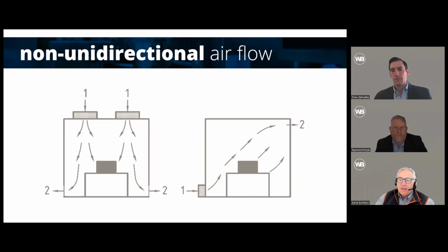Right. And along those lines, another question: do clean rooms recirculate air for energy efficiency reasons, or is it always supplied by fresh air intake? I think you answered that before. In most spaces, yeah, it's really a toxicology issue. In most clean room spaces, it's large recirculation. It's really in pharma or chemistry use or toxic use where you'd want to exhaust that out. And usually when you exhaust that out, you're going to exhaust it out to the atmosphere, out of the building, through another containment filter system to protect the neighborhood if it's a highly toxic space. So I don't want people to think you're just dumping it out of the building.